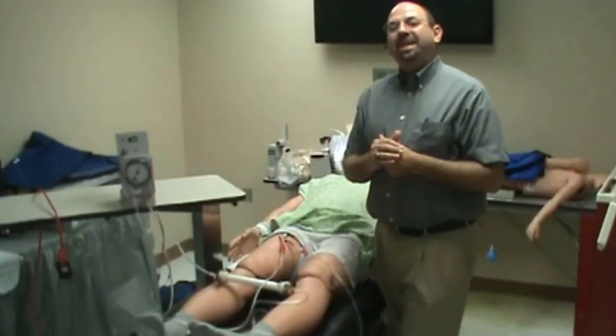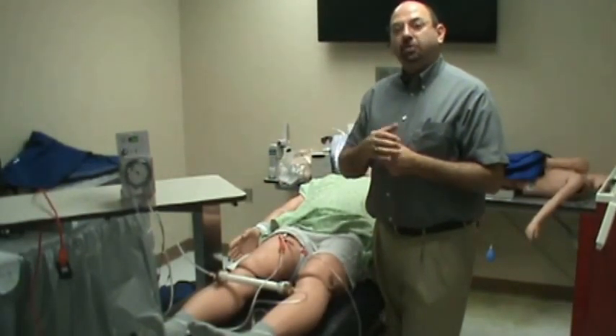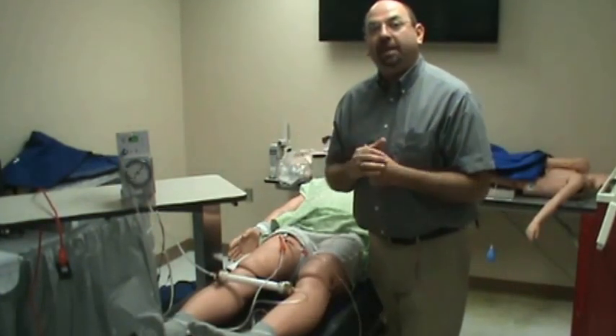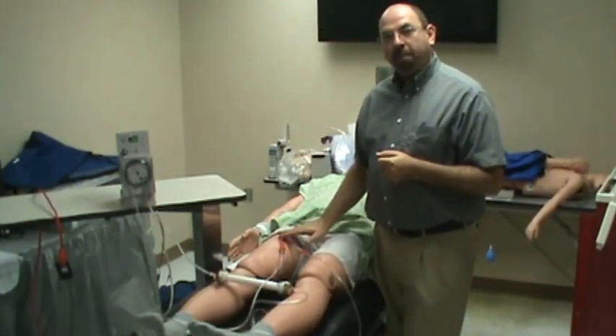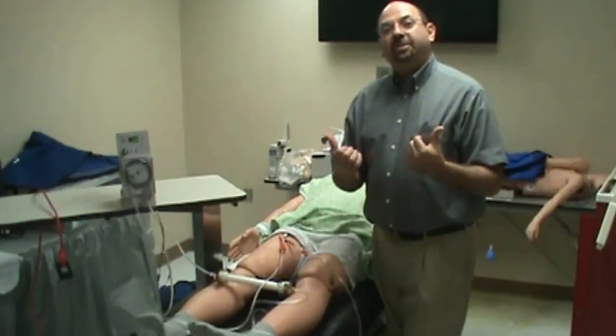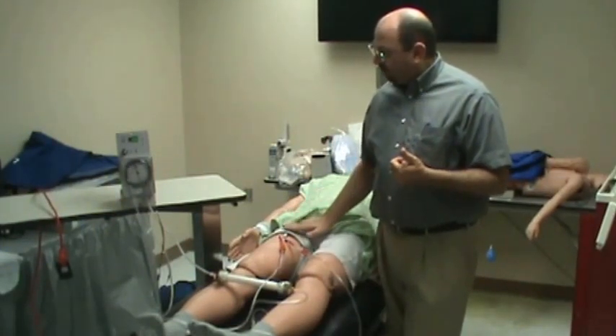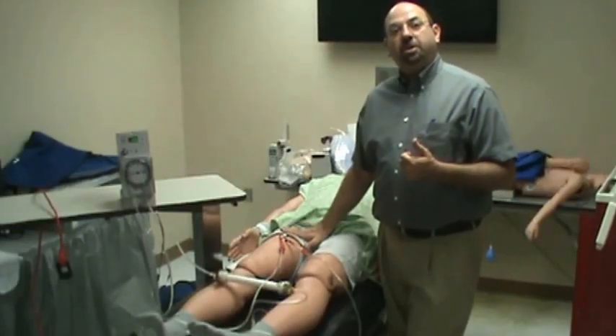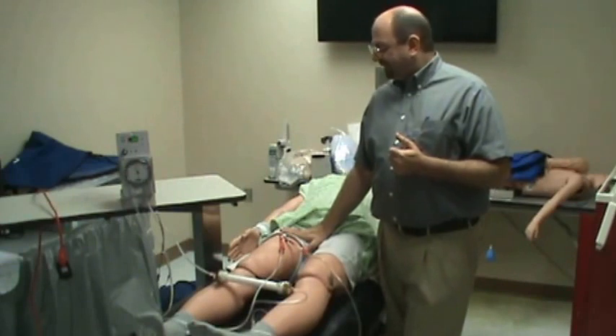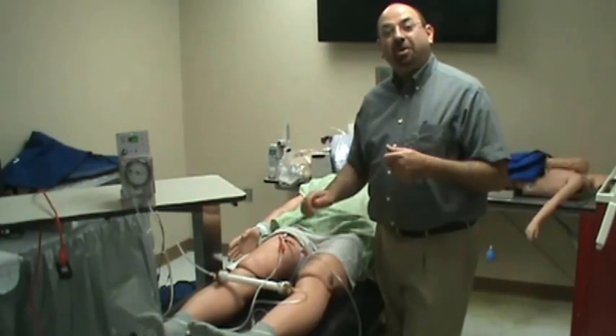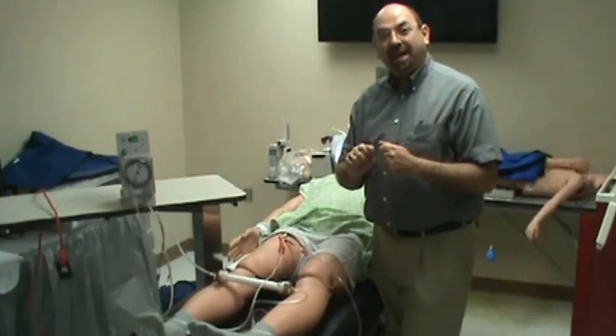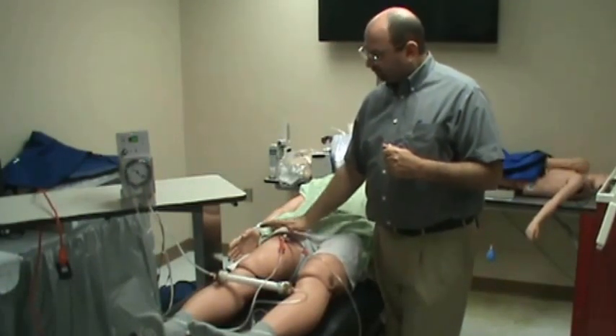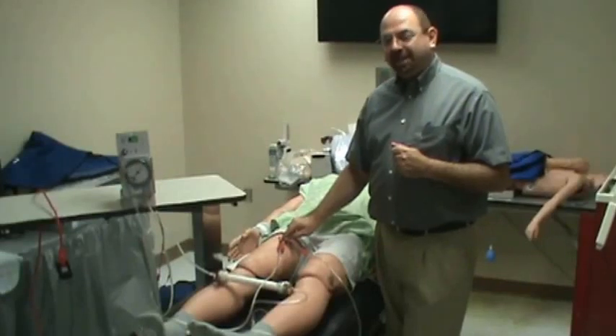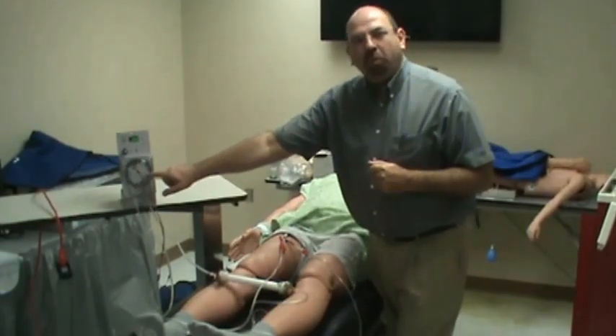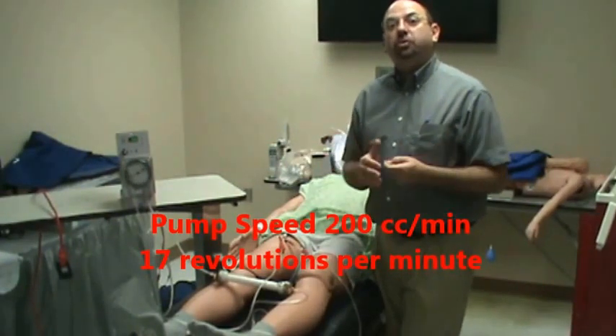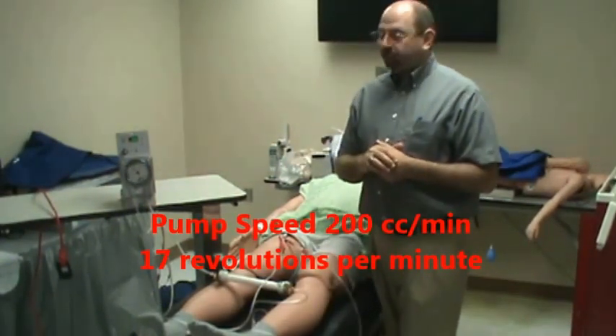Pump speed is preferred to be at 200. The reason I want it at 200 is that if you create a lot of negative suction and negative pressure, there is a chance of aspirating air. So I prefer to place a bio-occlusive dressing over the venous stick where the catheter is in, and make sure all the connections are really tight.